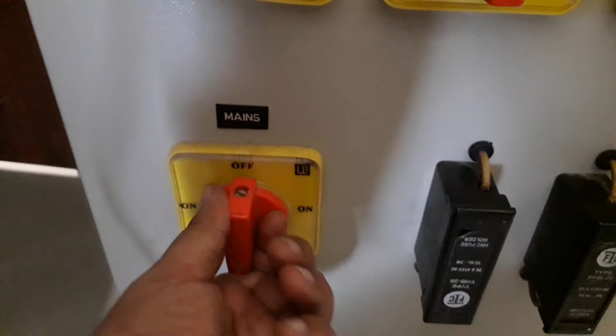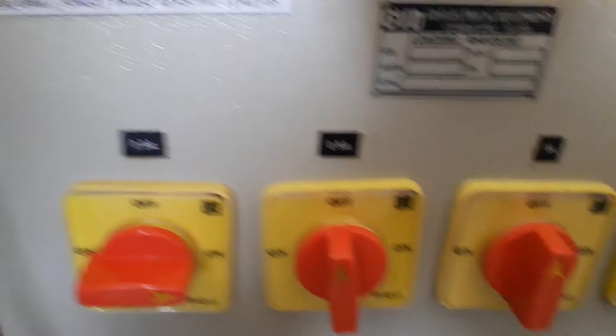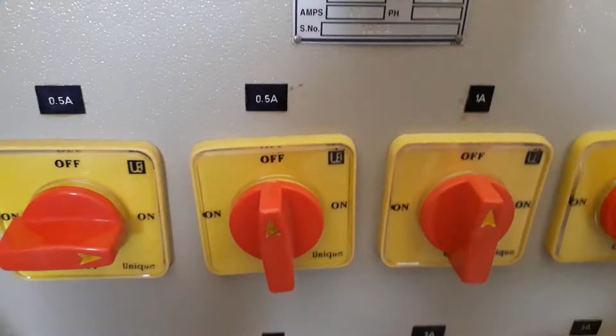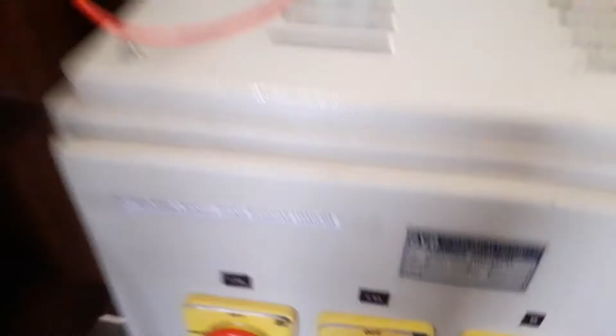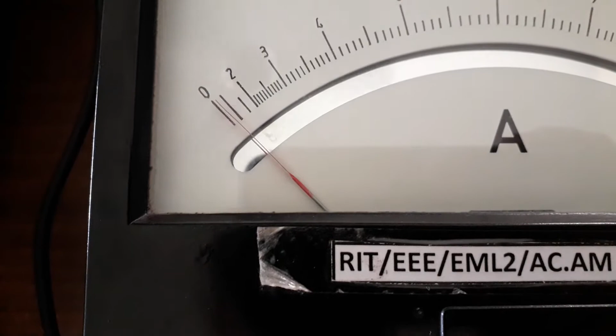For example, first you have to switch on the main of the load. After that you switch on the 0.5 amperes. Now for the 0.5 amperes, what is the reading here? See, now you have a small deflection in the secondary side ammeter, between 0 and 1, so about 0.5 amperes, but it is not accurately 0.5 amperes. Due to some drop it will show slightly less than 0.5, like 0.45 or 0.47. Note down the corresponding voltmeter reading.